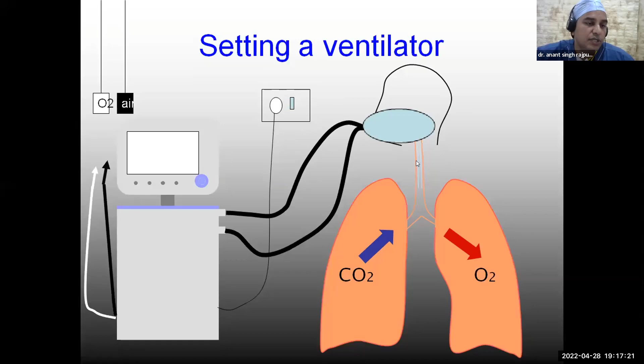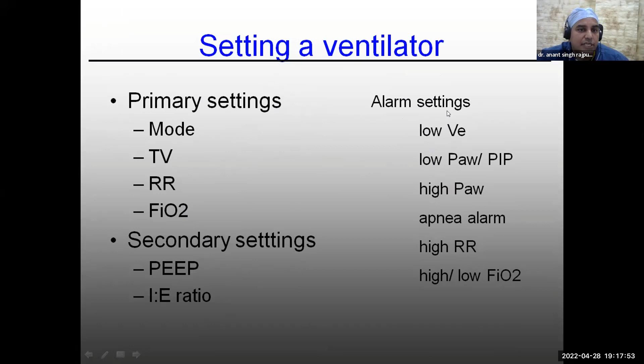What are the primary settings that we do on the ventilator? We select a mode on the ventilator, and decide the tidal volume, respiratory rate, and FiO2. These four things are the basic things that we do as primary settings. The secondary settings will be PEEP and IE ratio, followed by alarm setting. Depending on the mode and the different strategies that you use in primary and secondary settings, you have to set the alarms accordingly. This is the most important aspect of setting a ventilator, that is, alarm setting of the ventilator.